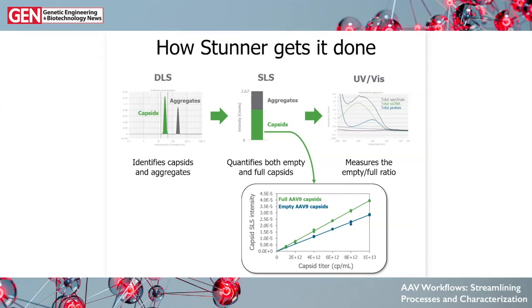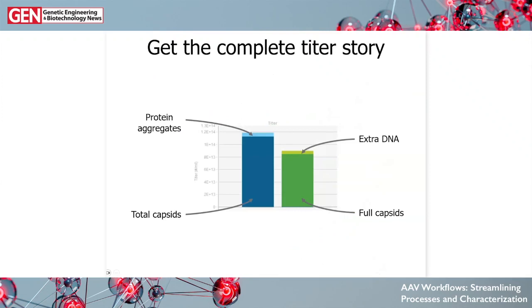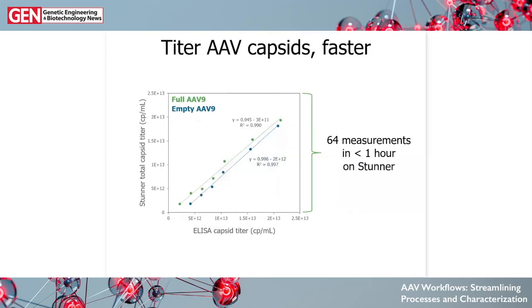Stunner calculates capsid titer by reading SLS intensity — say 2×10⁻⁵ — which gives a range of capsid titers that could fulfill that intensity. To get down to a single answer, you need the empty/full ratio to know where in that line you lie based on how full your capsids are. You combine the SLS and DLS information with the UV-Vis information to get to one accurate capsid titer number. From all that data, Stunner understands the complete titer story: total capsids, excess protein signal from aggregates, full capsids present, and excess DNA.